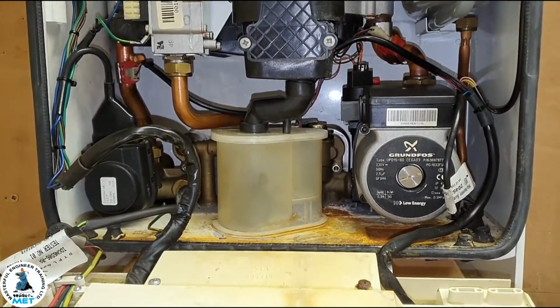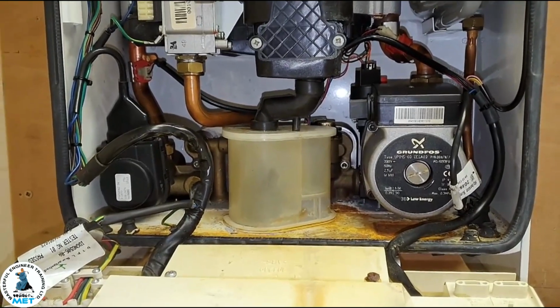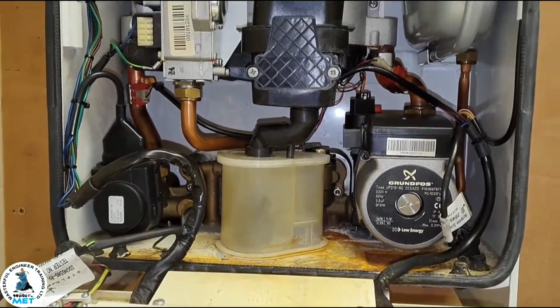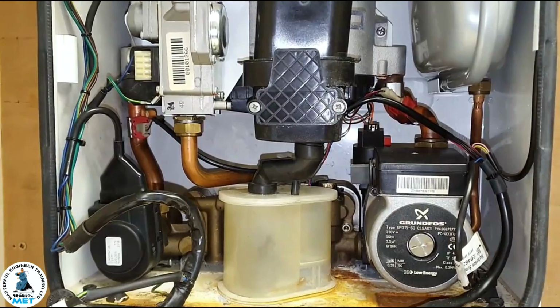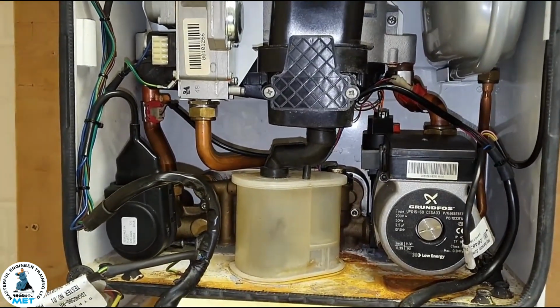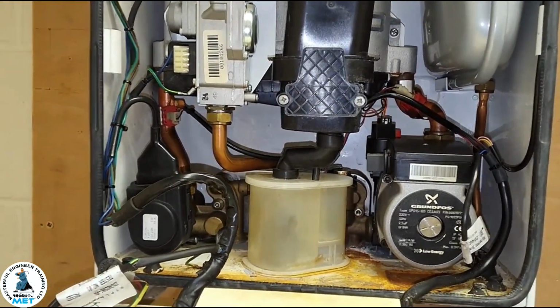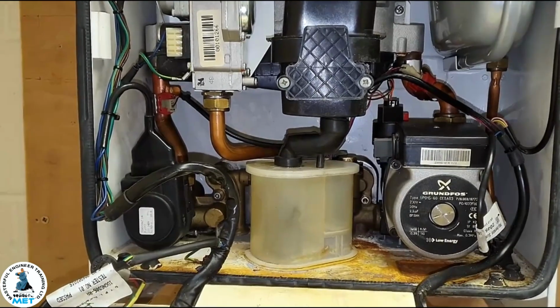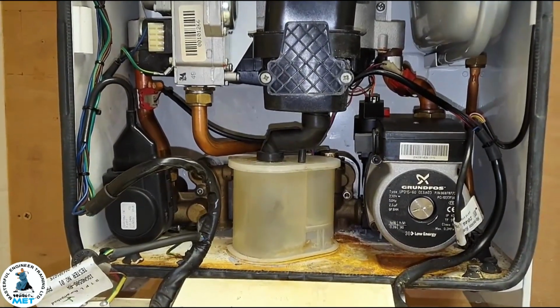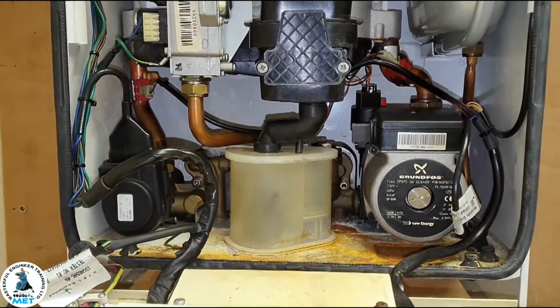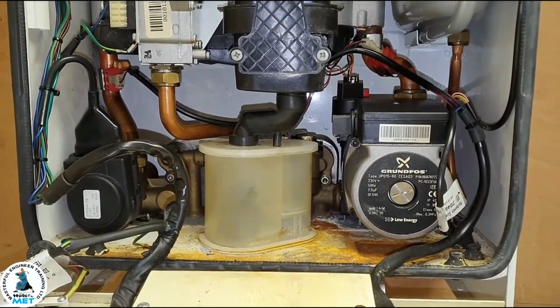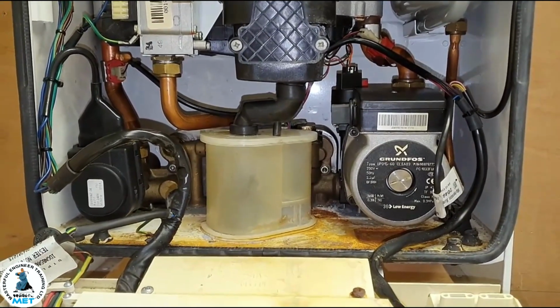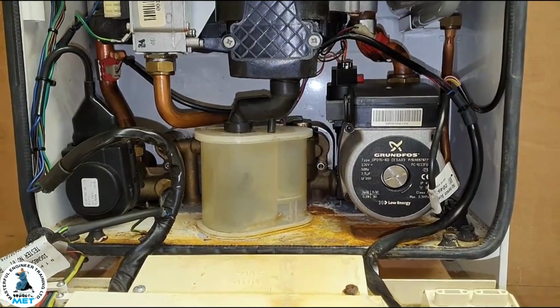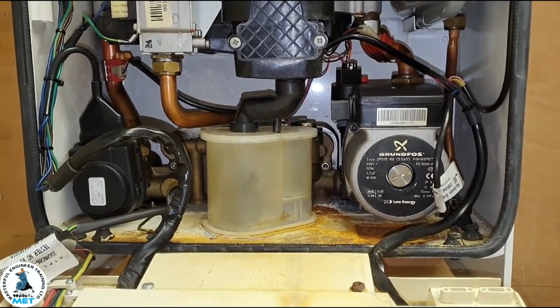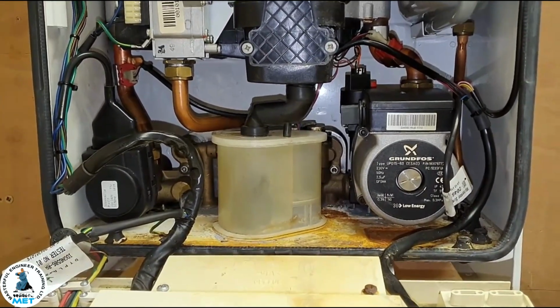Now on the other side, B, you ask: when does it happen? Does it happen when you put the heating on? Oh yeah, the hot water's fine, but it happens when you put the heating on. Okay, red flag - it's over-expanding. So you just turn it on and monitor it. If it starts creeping up after 5 minutes, then it's your expansion vessel.